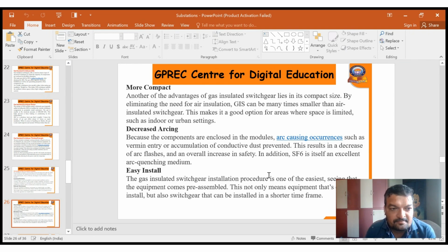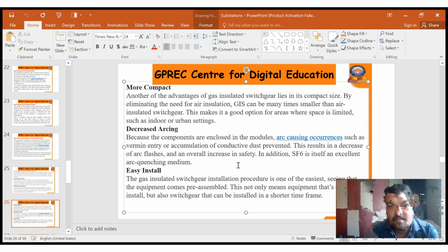Next, the sixth one is easy installation. We know that the gas insulated switchgear installation procedure is simpler because the equipment comes pre-assembled. This not only means that the equipment is easier to install, but also that the switchgear can be installed in a shorter time frame. That is another advantage of using a gas insulated substation.